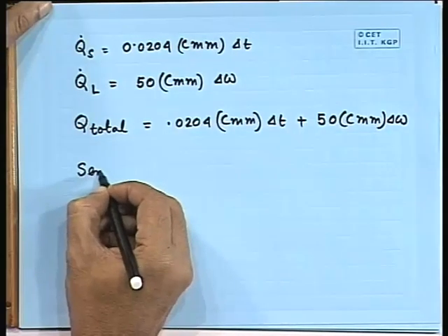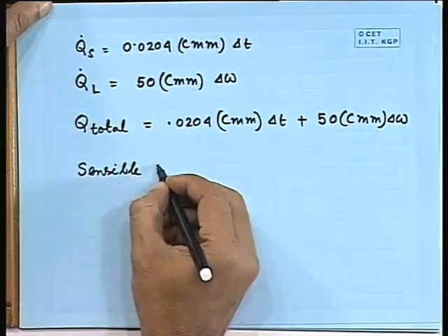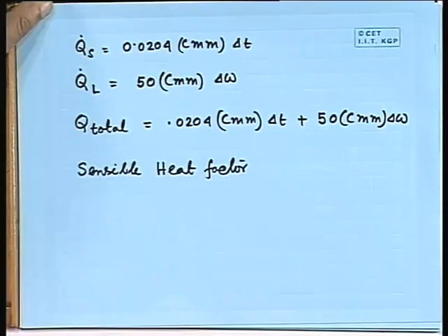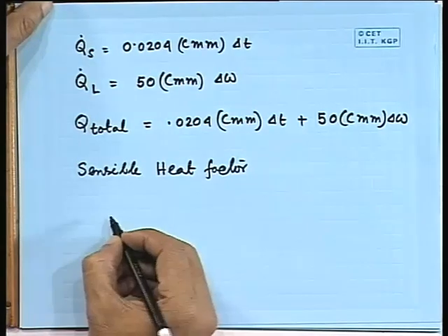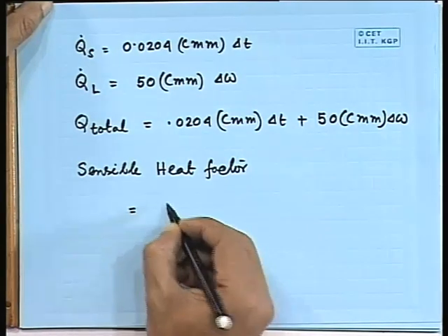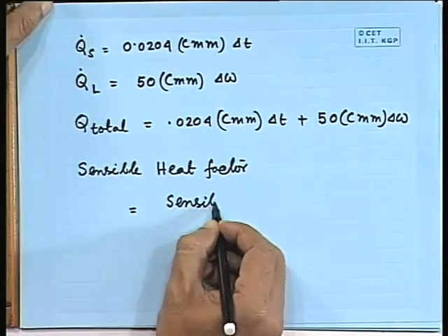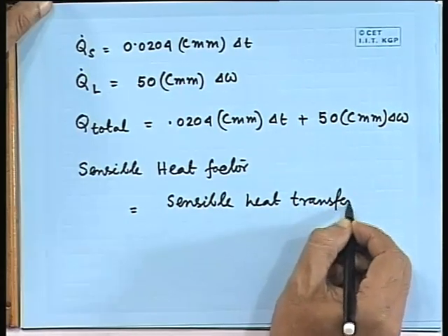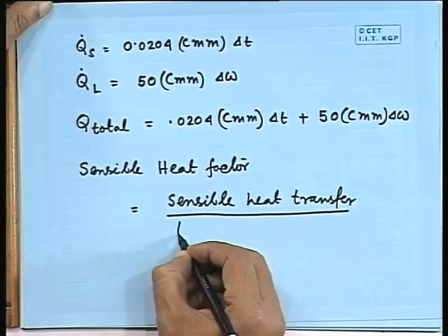All right. Now, generally we define one quantity here which is known as sensible heat factor. What is sensible heat factor? Sensible heat factor for any process is equal to sensible heat transfer divided by total heat transfer.